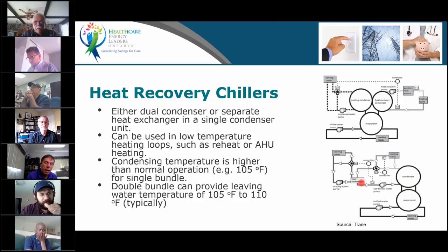Well, like I said, it's kind of case by case, but if you have a low temperature loop and you have cogen, I would tend to say yes. You won't be able to take a high temperature loop system where you have no low temperature and say, I'm going to use a heat recovery chiller. But if you have the stability of recovering the condenser heat and sending it to a loop, yes, I'd say at first glance, it would be a good thing to have.